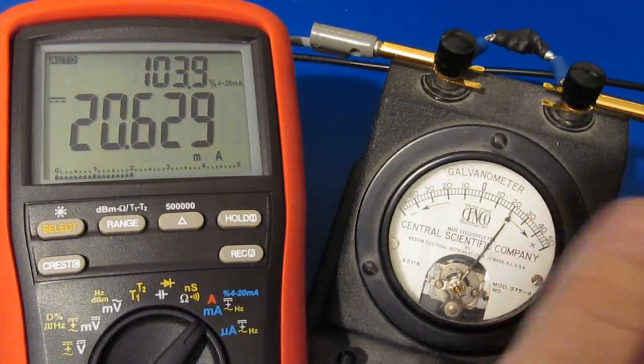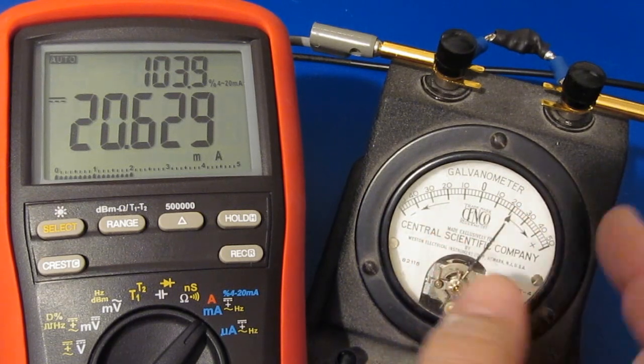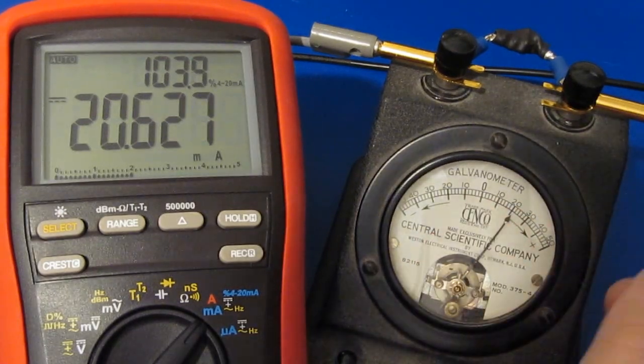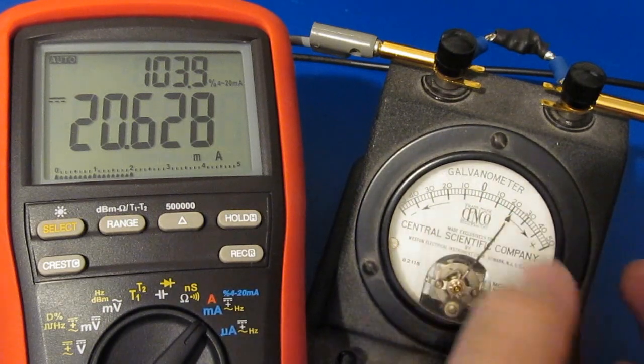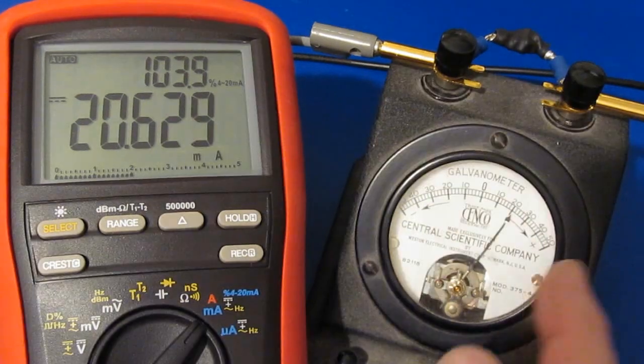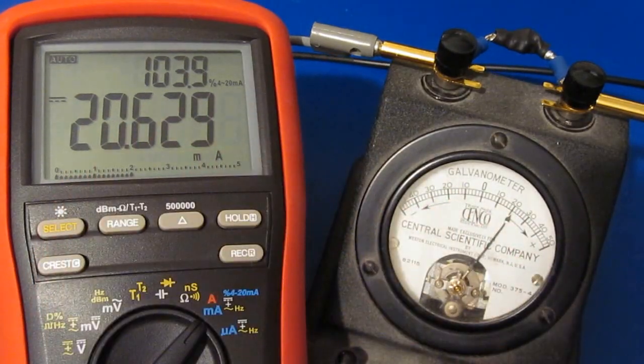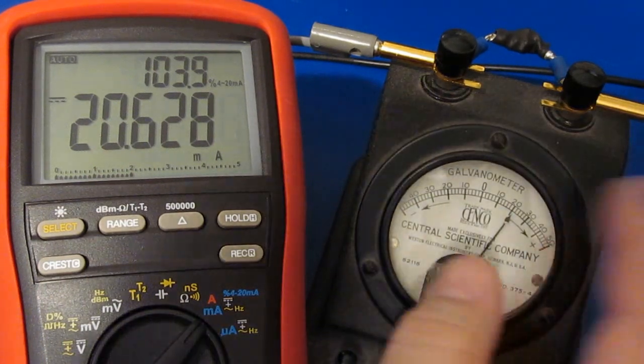We're reading a negative current this direction, and if I flip the two leads, now we can see it's reading on a positive scale. To look at current signals in the 4 to 20 milliamp range really isn't a problem for even an antique meter like this. It's just a question of setting up a shunt to get the scaling that you want.